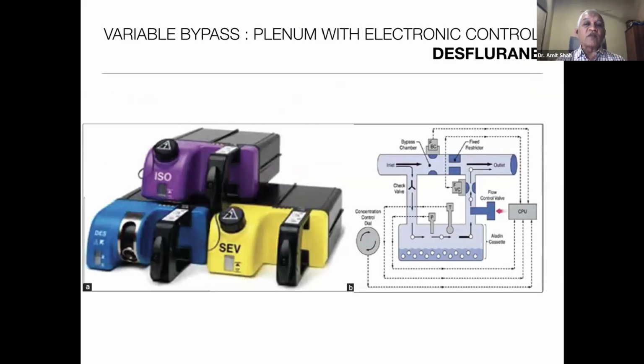Now, a word about the desflurane vaporizer in the Aladin cassette. In the Aladin cassette, it is still a variable bypass type of vaporizer, because it is still measuring vapor pressure and temperature. So the Aladin cassette is more or less similar to the variable bypass. It is a plenum with electronic control for desflurane. It does not require separate heating. It just measures the vapor pressure and temperature and accordingly varies the flow through the bypass chamber and the vaporizing chamber.